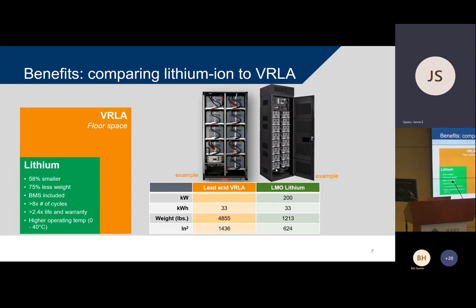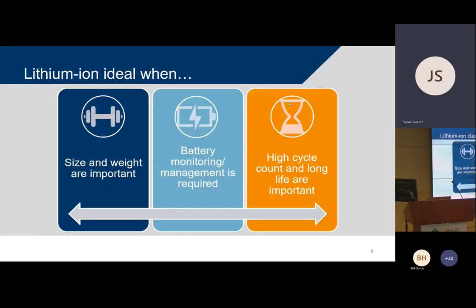Those are good reasons folks have been interested in lithium batteries, but there's more to it. One big thing is lithium batteries in this market offer a 10-year guaranteed performance life, guaranteed to produce at least 80% of day-one capacity all the way through 10 years, or the vendor will replace the affected battery or the entire string. So users don't necessarily have to budget for a full battery replacement every 5 years anymore; they can plan for up to 10, sometimes 15 years without replacement. That really impacts total cost of ownership.